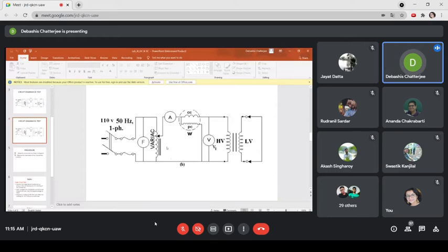Now if you perform the same test on the same transformer, normally the leakage reactance is of a low value, so the short circuit current is large, and you require a voltage of around 8 to 10% of rated value to flow rated current under short circuit condition in a transformer. If you remember your theoretical courses, it requires a voltage of around 8% to flow rated current through the transformer.